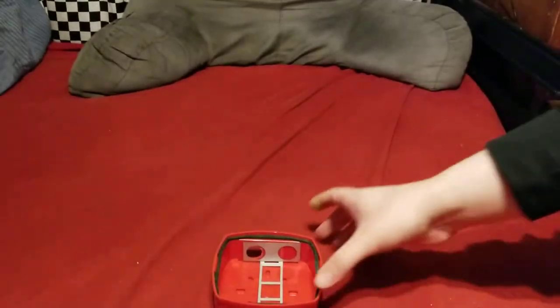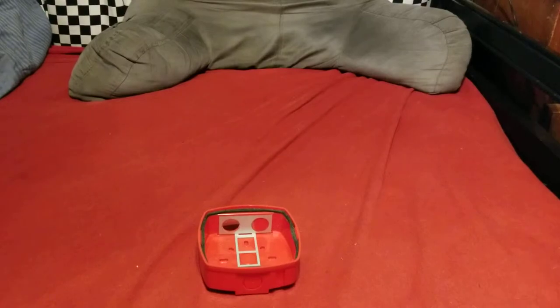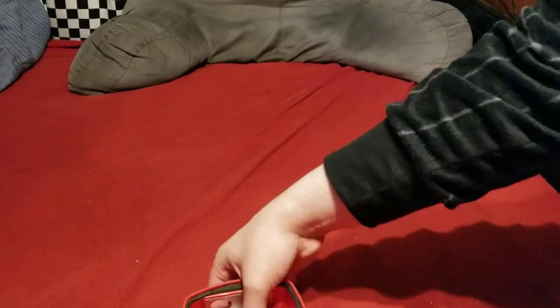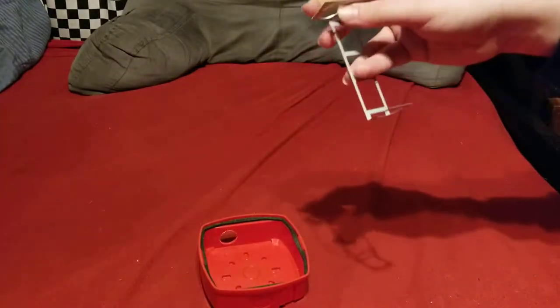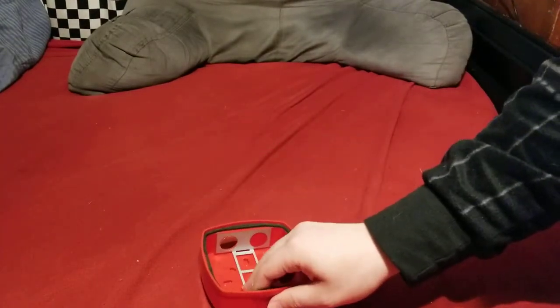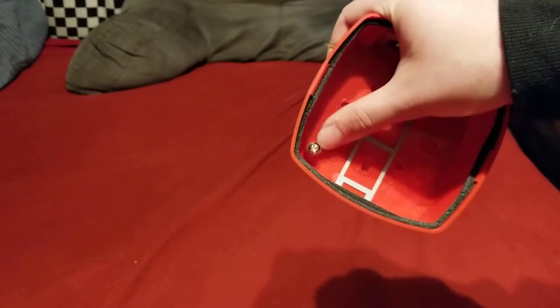This is a deep base sounder. The deep base is obviously for the IP rating to make it weatherproof, and it also comes with this little wall gasket that you're supposed to stick on the back of the alarm. Inside of it, there's a little metal bracket to help seal the wire knockouts, and there's also a little terminal for an earth ground connection.